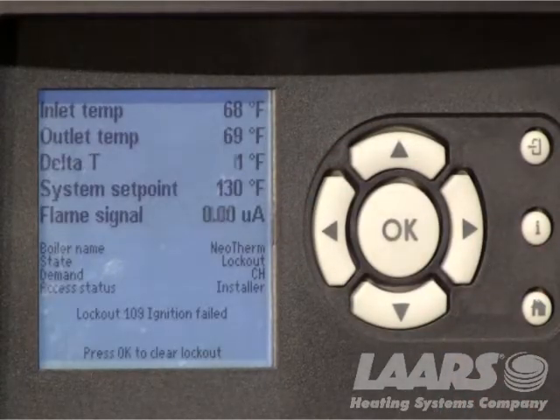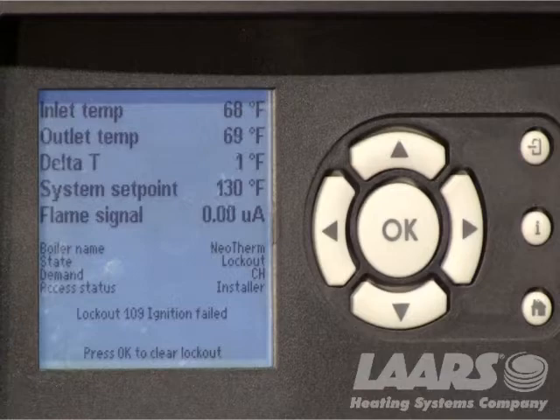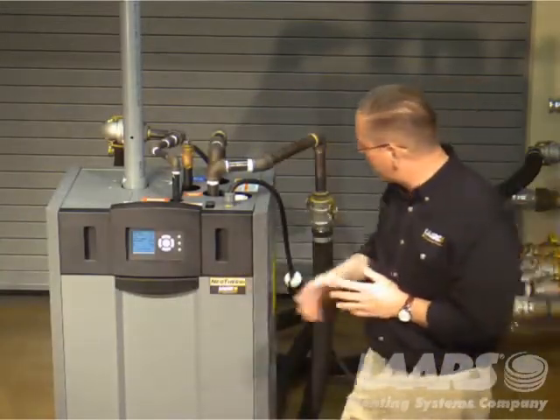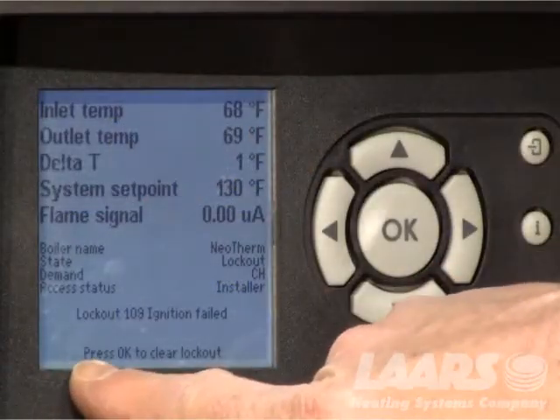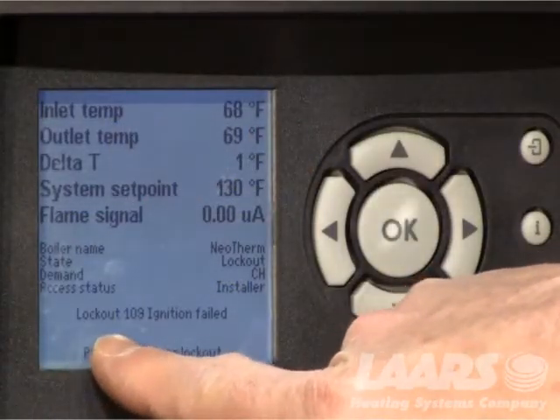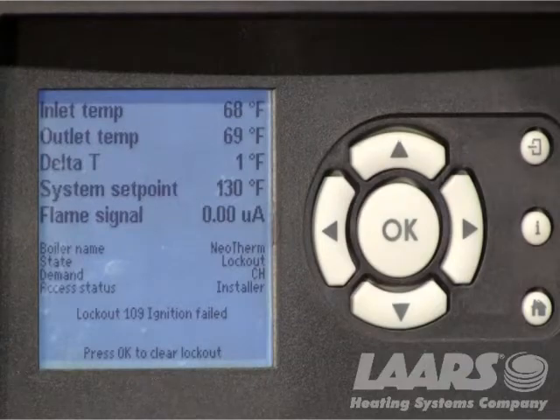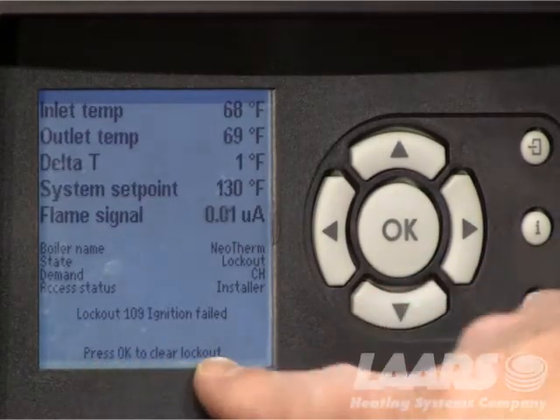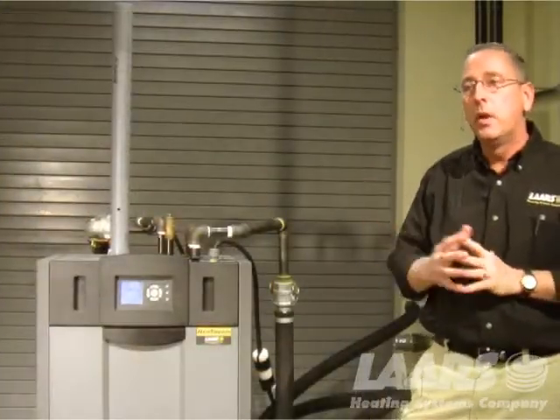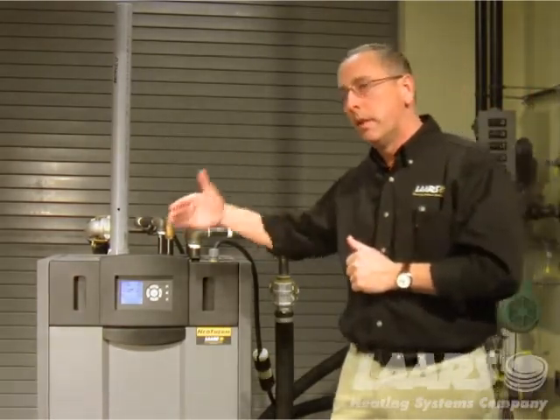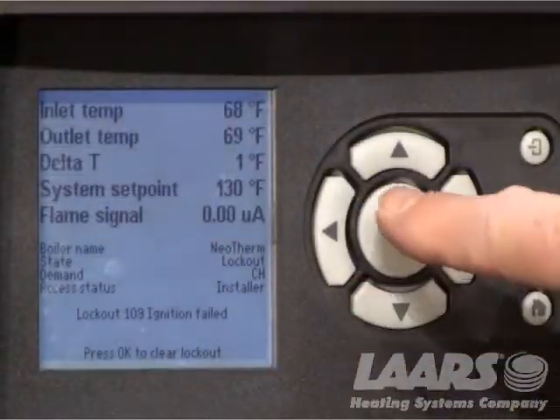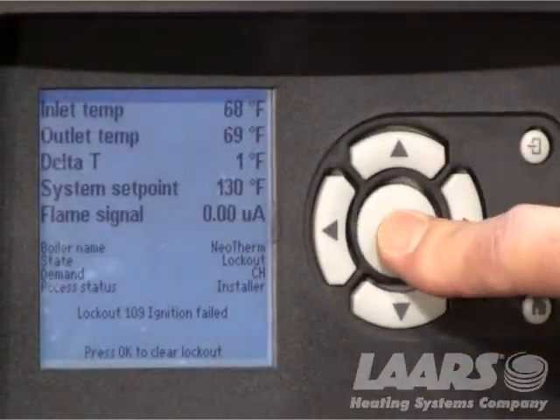I'm going to go back to the home screen and what I want to show you here is lockouts, in case you had a lockout and you didn't know how to reset it. For example, I've just locked this boiler out and it tells me lockout 109 ignition failure. It will also prompt us to press okay to restart. So if you had a lockout and you couldn't get your boiler running, this is what you want to look at. Simply press the okay button.